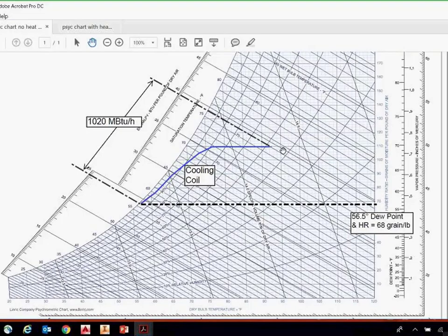Now, if we take in that example only a cooling coil, and again, we have a fixed capacity, 85 tons. We're seeing design temperatures of 92, 76. At that capacity, we're getting down to a dew point of around 56.5 degrees. And again, this is without a wraparound.